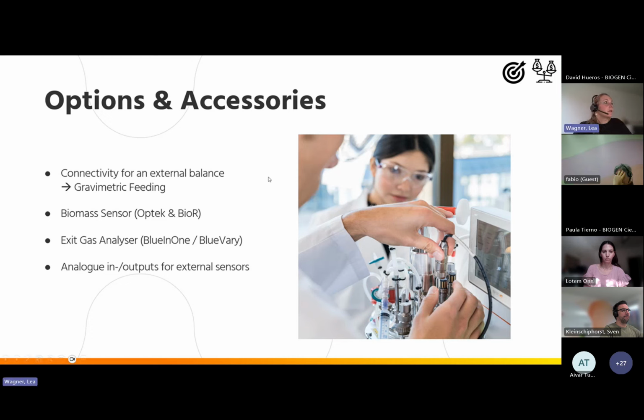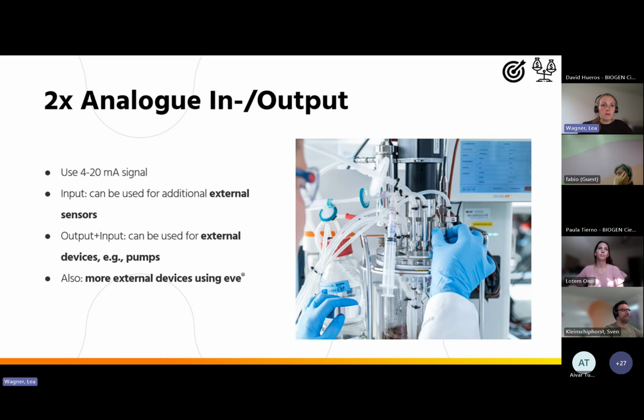And last but not least, we also have 2 analog inputs/outputs for more external sensors and devices. I will show you some examples on the next slide. So the analog input/output uses a 4 to 20 milliampere signal, and the input can be used for additional external sensors. So for sensors we do not offer, maybe the customer wants to add a sensor to measure metabolics, like lactate or glucose concentration. The input/output can also be used for external devices, for example, an external pump. We offer the one from Watson-Marlow, or also to connect, for example, an external perfusion system to run a perfusion process on Minifors 2.